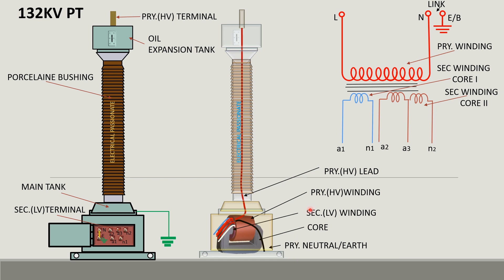HV terminal to body or earth, HV terminal to secondary core 1, HV terminal to secondary core 2, body or earth to core 1, body or earth to core 2, and between core 1 and core 2.